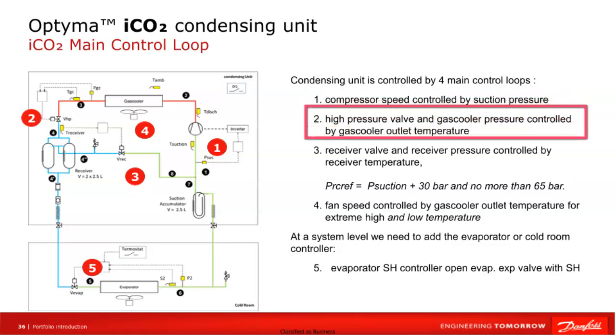High pressure valve regulates the pressure on the gas cooler depending on the temperature at its outlet. The valve adjusts the pressure on the gas cooler depending on the outlet temperature.